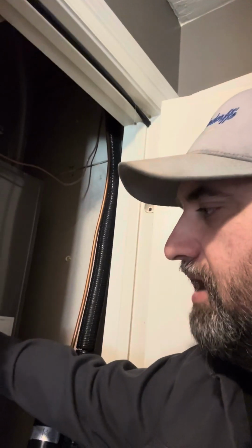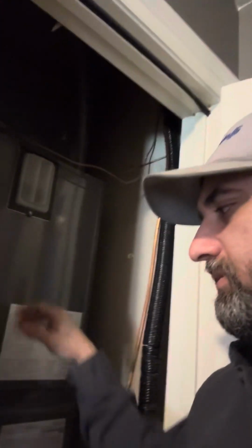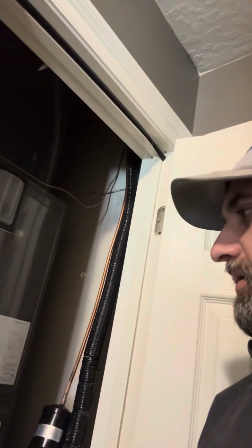my next stop would be outside. You can go outdoors, and again, you have diagnostic lights on the board outside. So pull the panel off, see if you have any diagnostic lights. Check your power, see if you have 24 volts, see if you have high voltage. See if your contactor's pulled in. If your contactor's pulled in, then most likely you might have a bad capacitor or something.